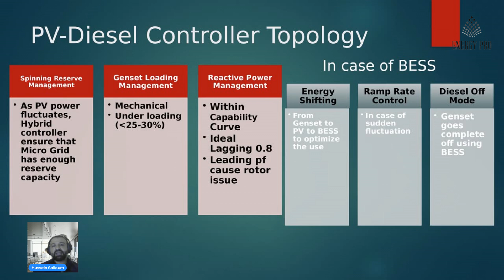So here we come to the question of Harry on the design criteria for an on-grid hybrid or off-grid hybrid system, including the battery. First, we have to know whether it's an on-grid or an off-grid system. If it's an on-grid system, we first look at the kilowatt hour, the energy consumption, not the power consumption, because the grid will cover the power. So we have to see what the load profile is during the day or the night, or if there are different types of load during the day and during the night. So here we look at the kilowatt hour, and then we look at the space available for the PV, and then we see if there is any limitation from the utility on the percentage of solar that needs to be applied in the system. That's in the case of on-grid.